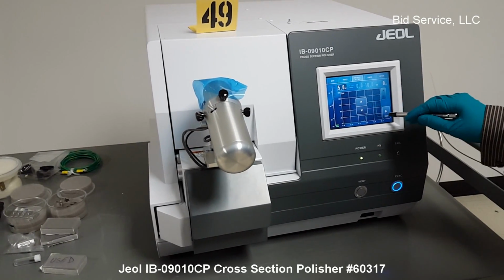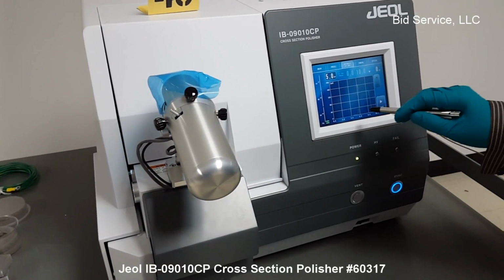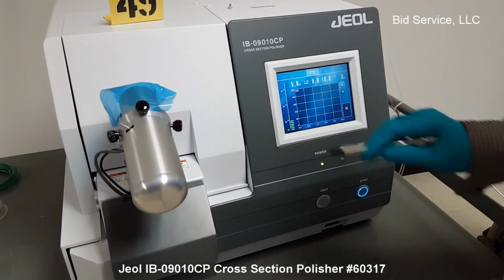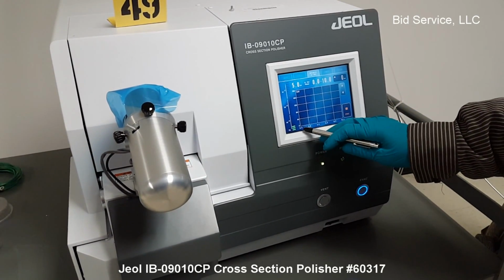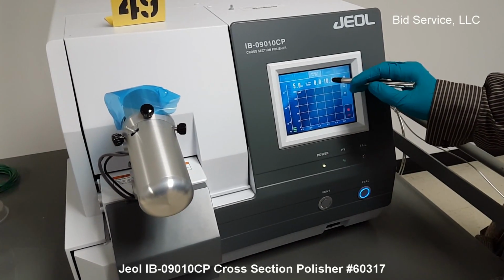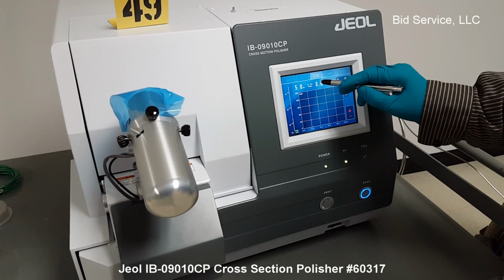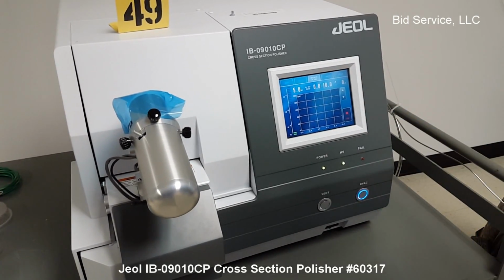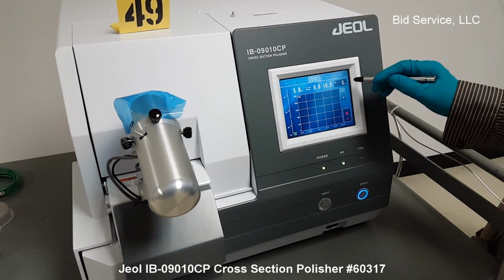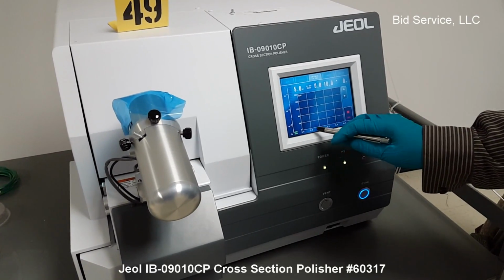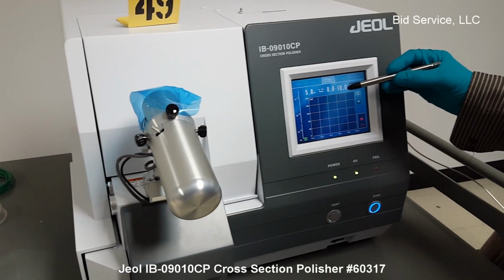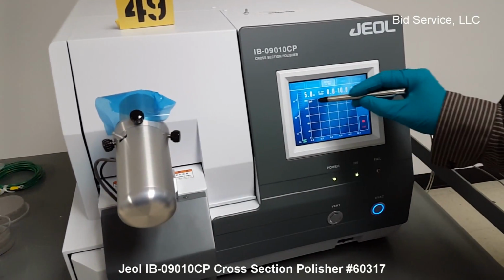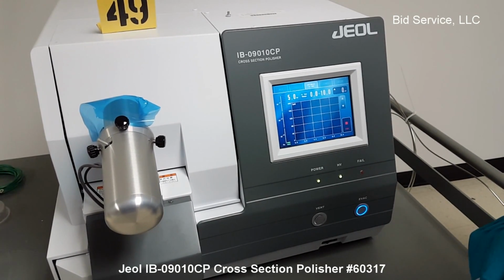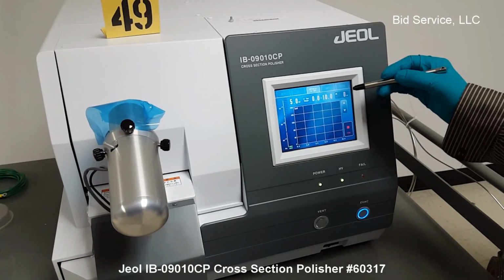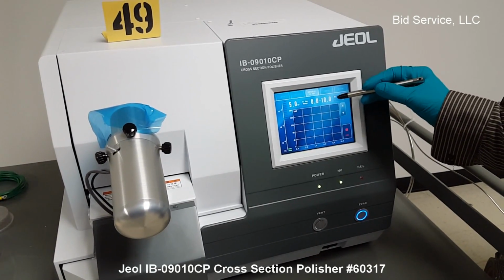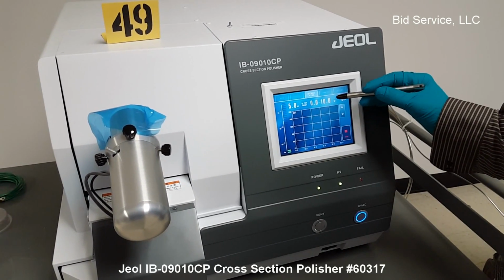And then once we start this, the chamber will be purged first, and then the gas flow will be increased for the set range. It can be set 0 to 10, or 1 to 11, or 2 to 12, and so on. Once the gas flow starts increasing, the ion current will start showing up. It's a 3 minute process, and it's possible to select a high current or a low current by selecting one of these arrows, either low current or high current.